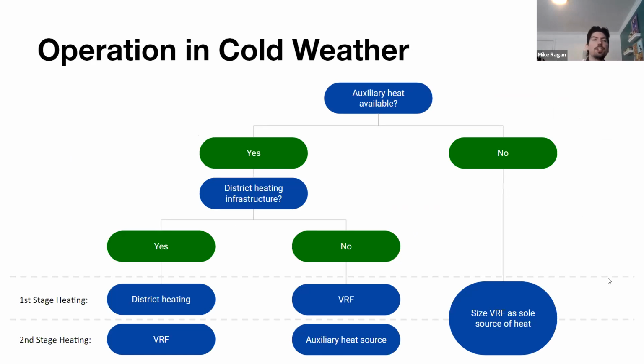So here's a decision tree of just how we would go down the process of determining what type of auxiliary heat, how we would integrate auxiliary heat into our systems. We would first ask the question, is there an existing system available? If not, then you're going to have to size that VRF system as the sole source of heat. You're going to want to accommodate for any derates you may see in that particular climate and size the system accordingly. If you do have auxiliary heat, great.